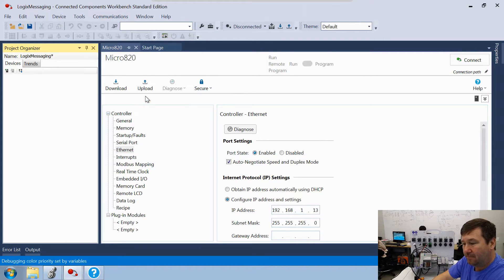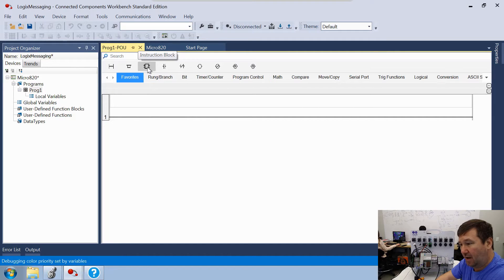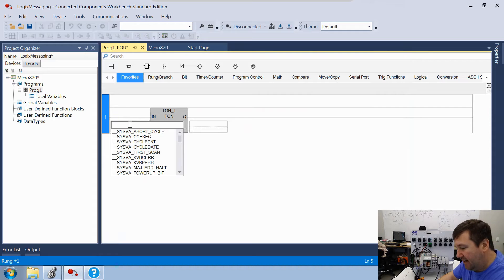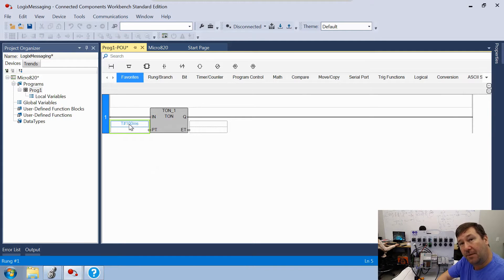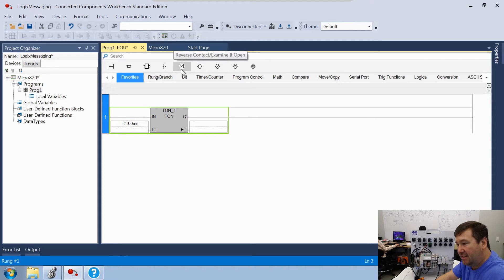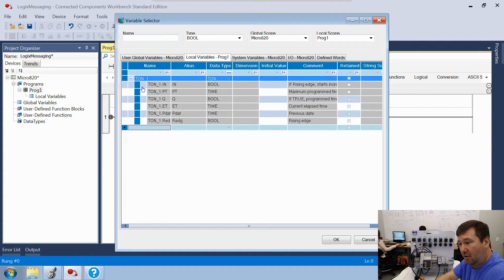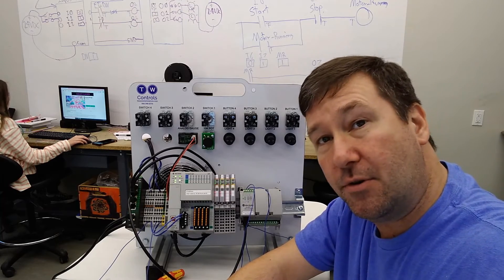Let's add a ladder diagram and open that program. First we're going to use a timer to create a sample rate — we've done this before so I won't go into too much detail. Drag an instruction block down and use a TON (timer on delay), setting the preset to T#100ms. This creates a 100-millisecond timer, so every 100ms we'll read data from our ControlLogix or CompactLogix PLC. Then drag down a reverse contact (examine if open) looking at TON1's Q bit — this Q bit will be true for one scan every 100 milliseconds.